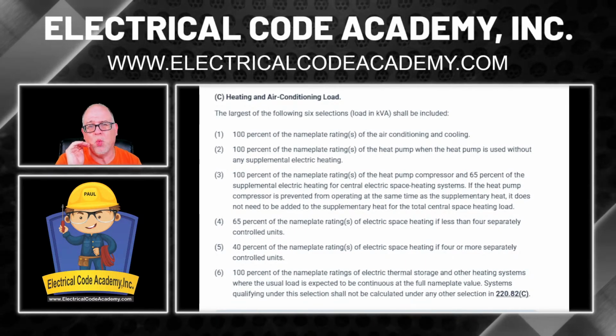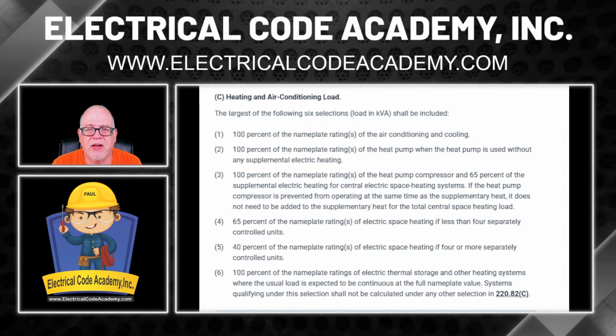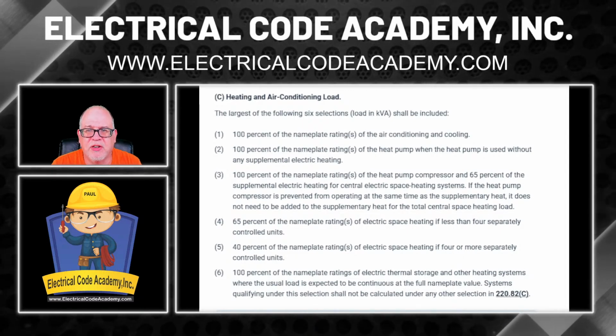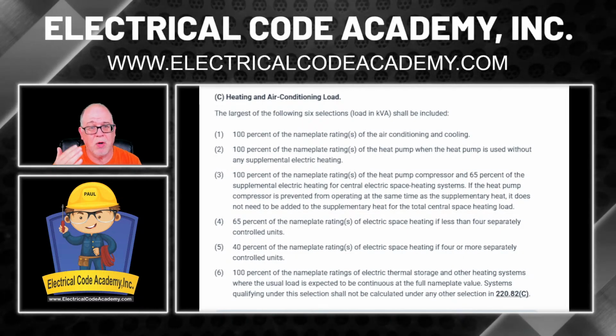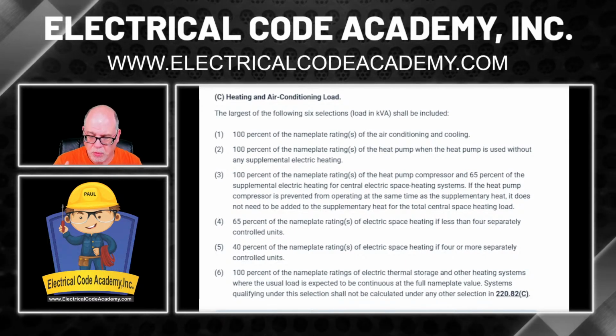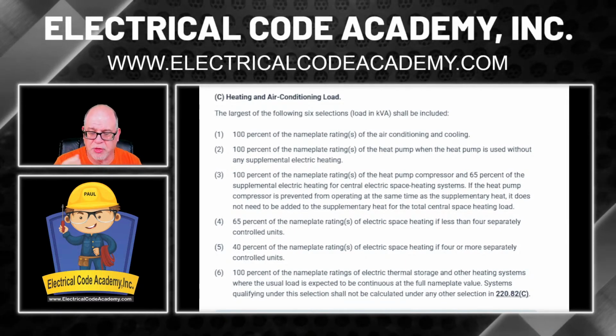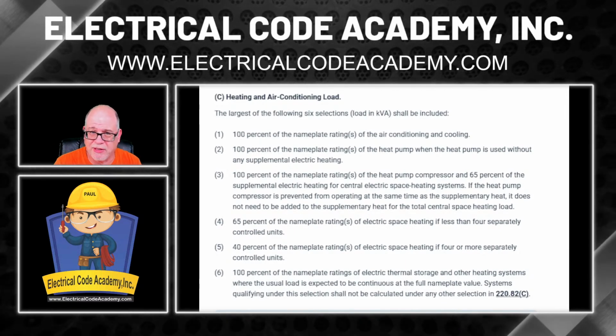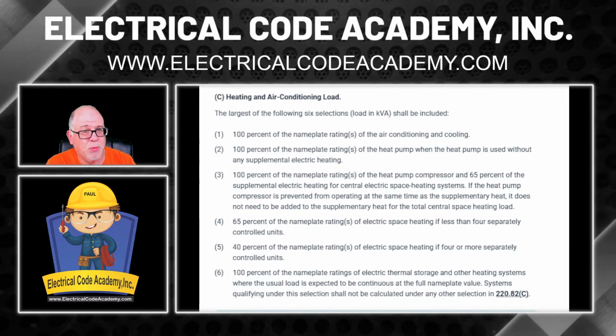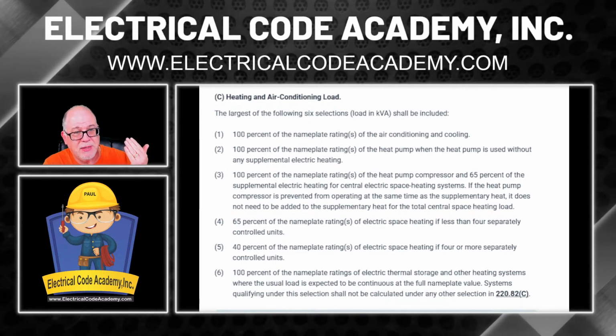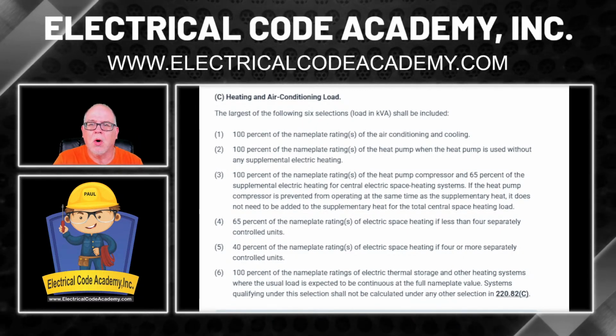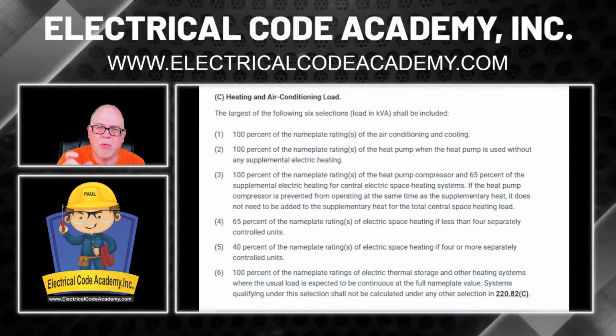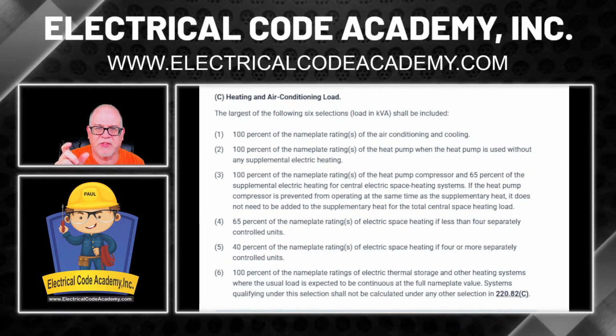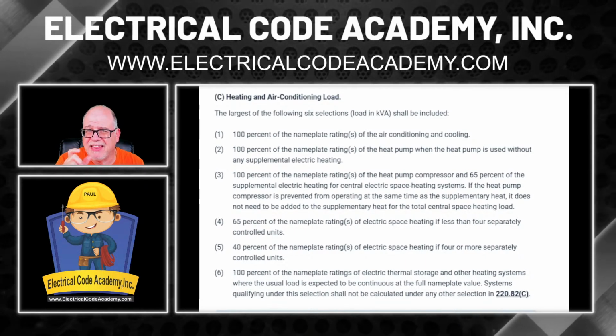Well, number 1 on this list says 100% of the nameplate ratings of air conditioning and cooling. Well, we already know what our air conditioning is. We had 2 of them at 10.5 amps and 3 of them at 7.2 amps. So we know what our air conditioning is. And we know our heat. There were 6 of them at 3 kW each. Okay, so we know that when it comes to the AC, we're going to take their full value at 100%. Now we need to see that heat.